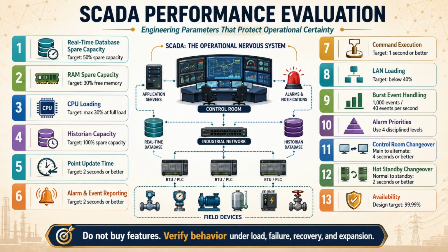Remote telemetry is not clean, fast, and local. It includes fiber links, radio links, leased lines, cellular paths, satellite paths, serial links, firewalls, gateways, latency, packet loss, intermittent recovery, and delayed event bursts. So the SCADA server must survive RTU silence, RTU recovery, buffered event floods, bad quality data, delayed timestamps, and command feedback uncertainty.